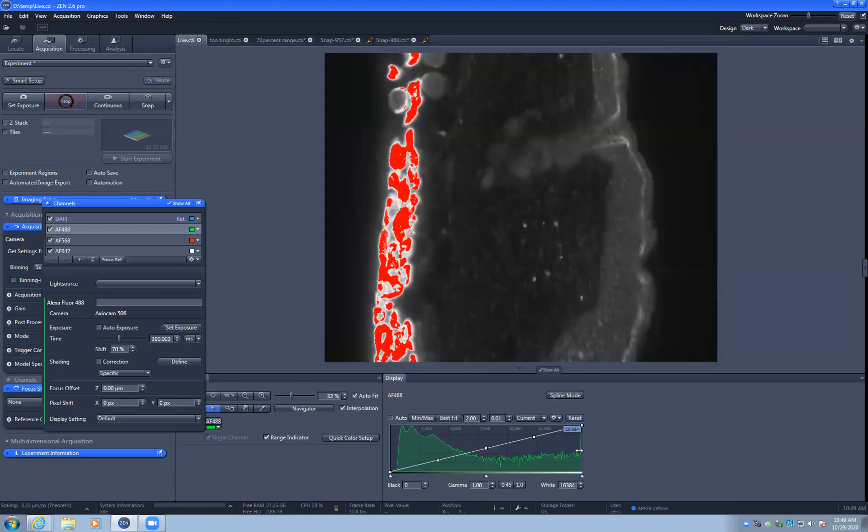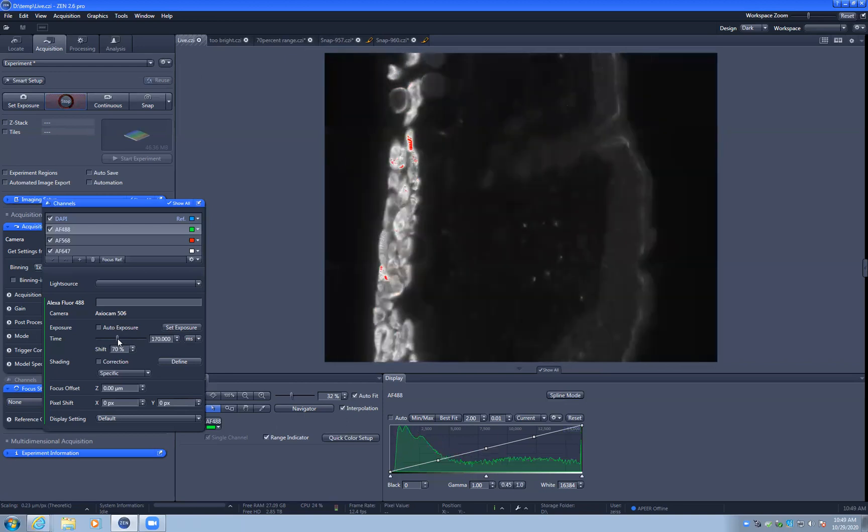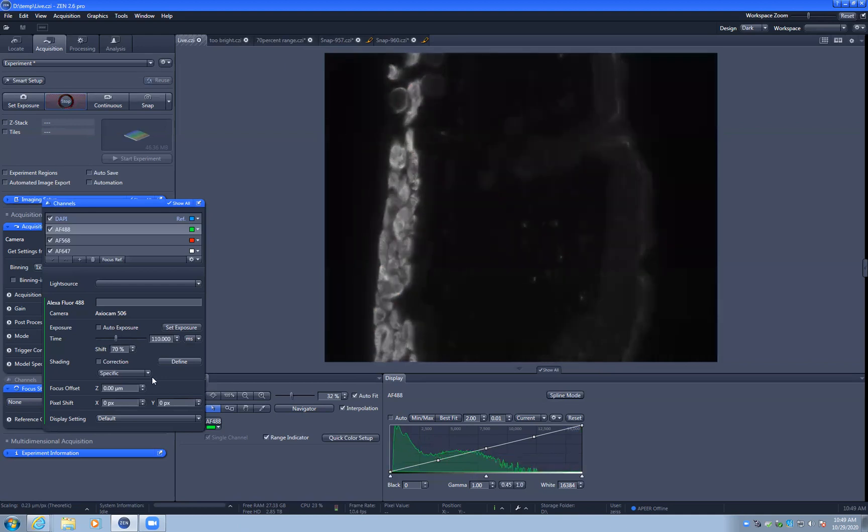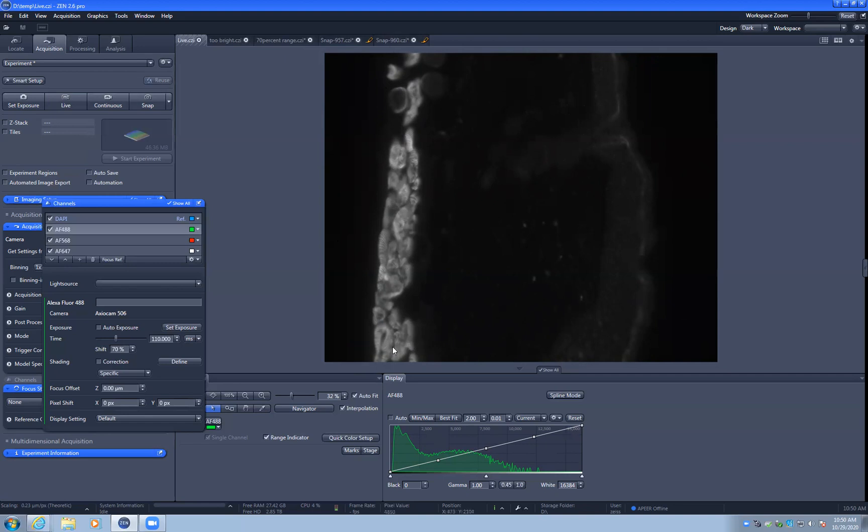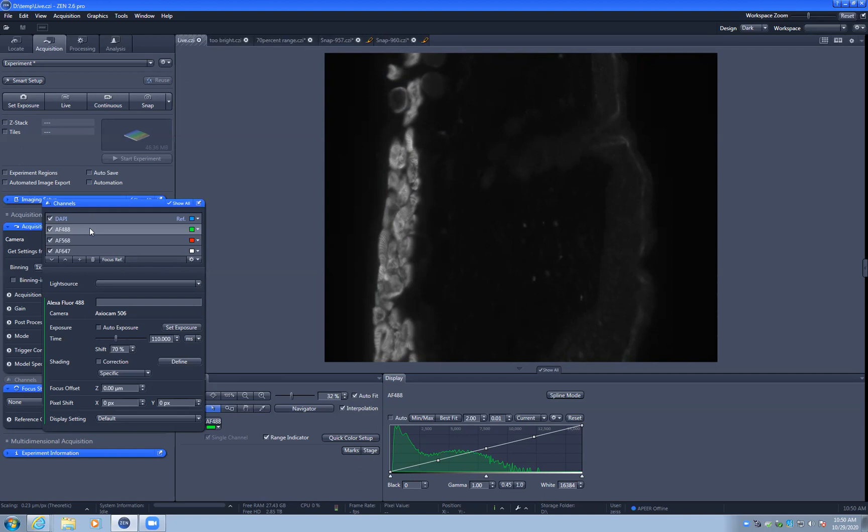So manually adjusting these times, we can just keep bringing the exposure time down, the amount of time light is collected for each picture, until the image is no longer saturated. That's one way to set the exposure time. Now, of course, if you're going to be looking at multiple slides for an experiment when you need to compare intensity, you need to figure out which slide is your brightest one, set the exposure time for that brightest slide, and then not change it for your other samples, so that they will all be relative to the brightest slide. You would have to do that for each color, because each color gets a different exposure time.